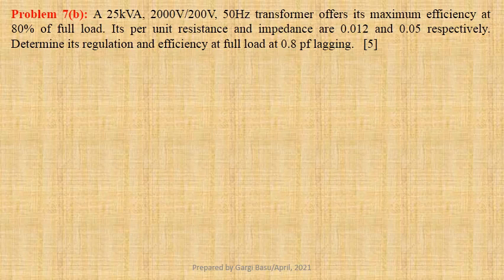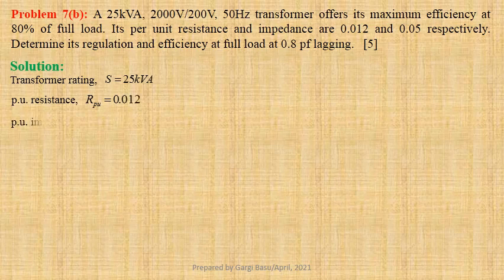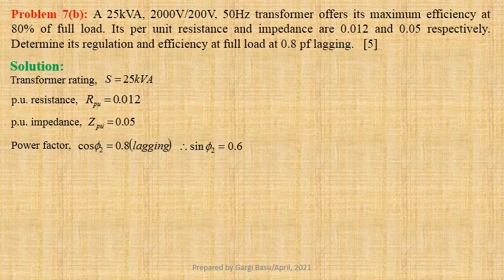Let us first jot down the given data. Transformer rating S equals 25 kilovolt ampere. Per unit resistance R per unit equals 0.012. Per unit impedance Z per unit equals 0.05. Given power factor cos phi 2 equals 0.8 lagging. Therefore, sin phi 2 will be 0.6. According to the problem statement, maximum efficiency occurs at 80% of full load. Therefore, we can write at maximum efficiency x equals 80%, that is equal to 0.8.